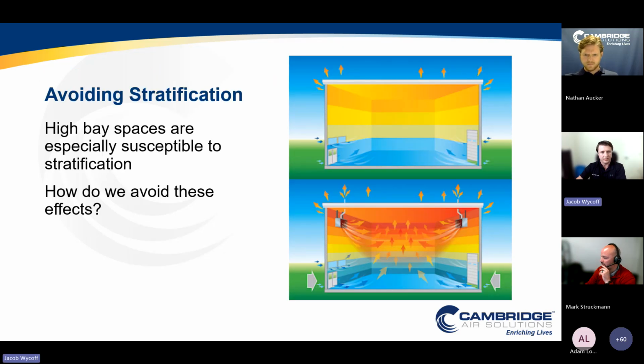Another question we get often with HTHV is how do we avoid stratification when we're discharging 160 degree air? We know that these high bay spaces are especially susceptible to stratification. They have very tall ceilings. They have cold air infiltrating down near the floor through open dock doors and man doors. That can oftentimes result in stratification, especially if they're heated by something like unit heaters, which have trouble getting the heat down to the floor and mixing the air throughout the facility.